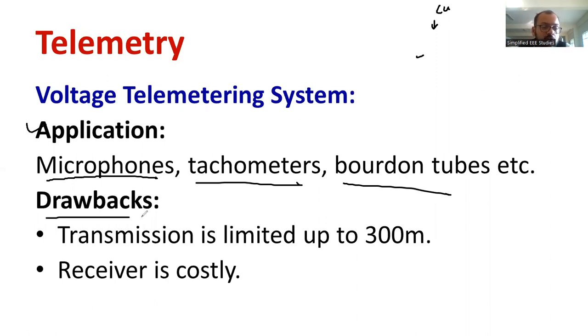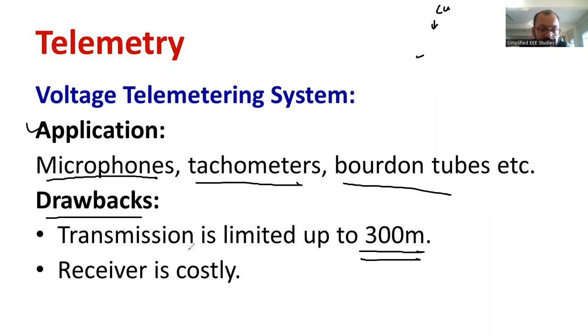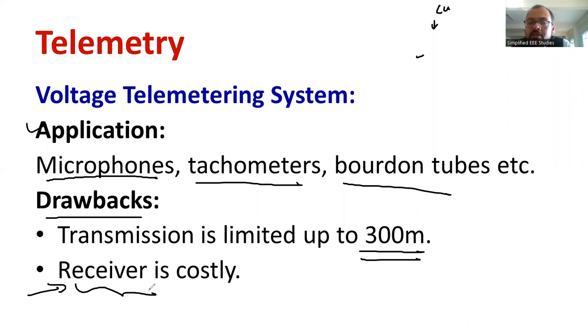What are the setbacks of the voltage telemetry system? The distance of transmission is a major constraint — only up to 300 meters. If you require more than that, you have to depend on a more advanced system. The receiver calibration is very costly and somewhat tricky; more technical knowledge is required. Basically, at the receiving end side the pressure is measured in terms of voltage, so calibration is one of the major challenges.